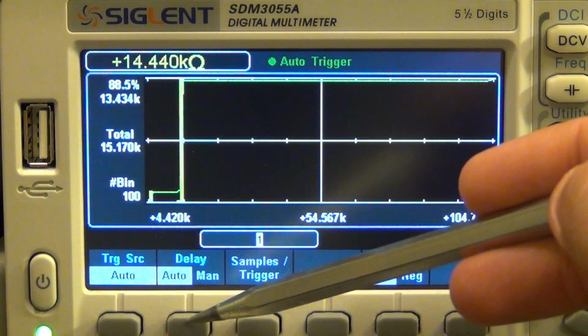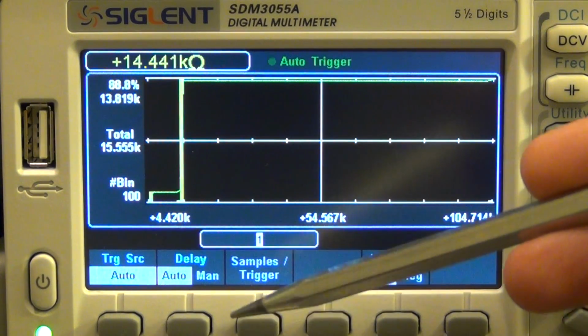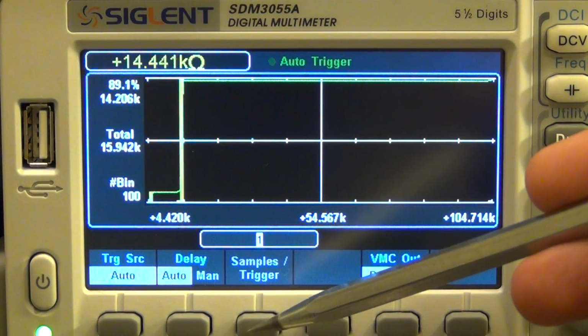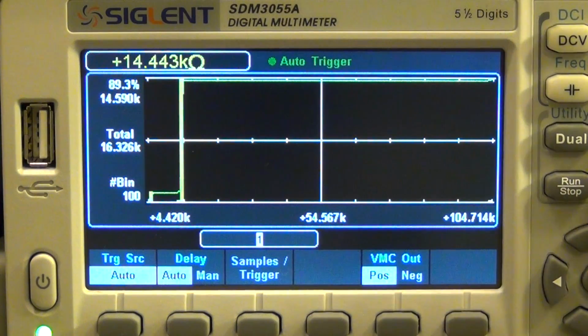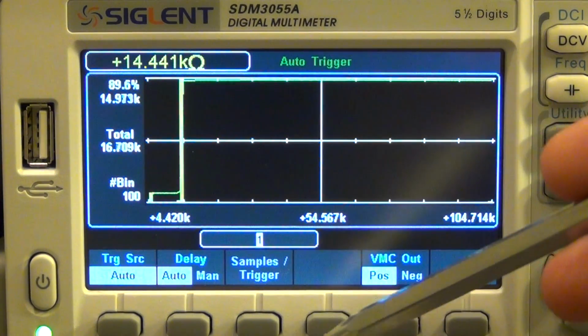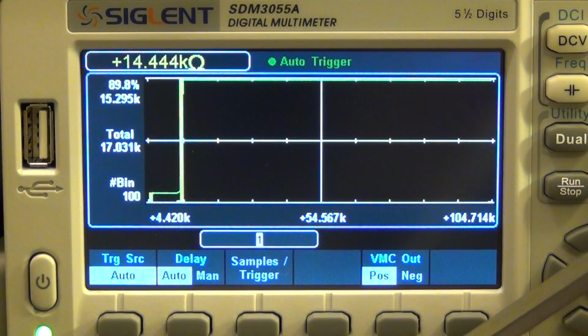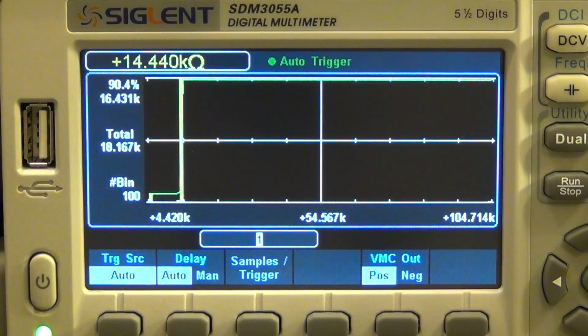Now the instrument does have a fairly good, reasonable set of acquire functions, so you can acquire with a certain delay as opposed to automatic. You can also tell it how many samples per trigger you want to set. So if you use the trigger option from the back, you can actually set how many samples you want to collect per trigger event, or if you just want to trigger individually, you can tell it how many measurements to take per trigger event. This can be pretty useful if you're collecting large amounts of data.